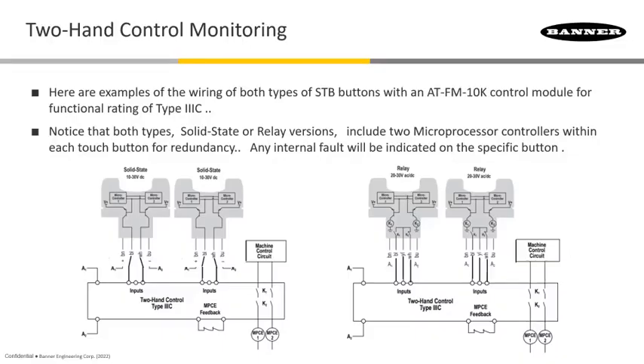This is just showing a couple of wiring examples of those STB buttons tied into an AT-FM-10K, for example. Notice that on both types — the solid state as well as the relay — there are two redundant microprocessors or micro-controllers in each one of these, and that's what gives us that highest Type IIIC rating. Any internal fault that is caught is going to be something that can be seen actually on the button itself.